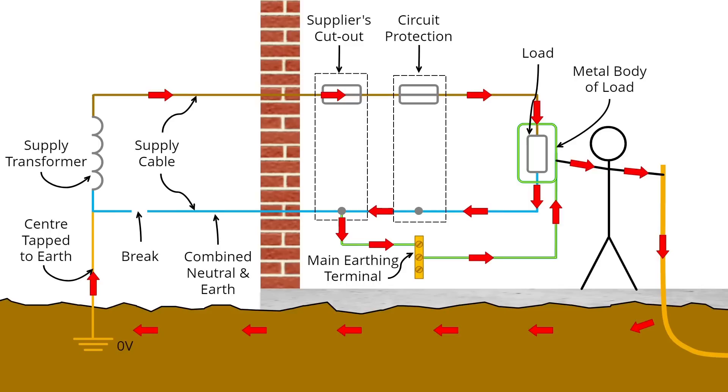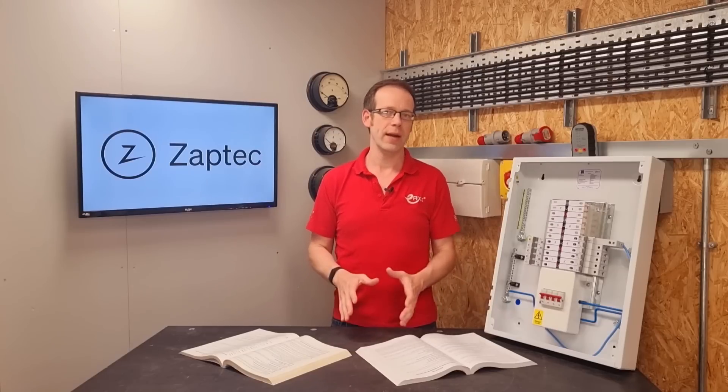Inside the property we can resolve this problem by connecting all the exposed conductive parts of a circuit to the extraneous conductive parts via the main earthing terminal, which means that all the metal work is at the same potential and a person is much less likely to get a shock to the literal earth that we walk around on.